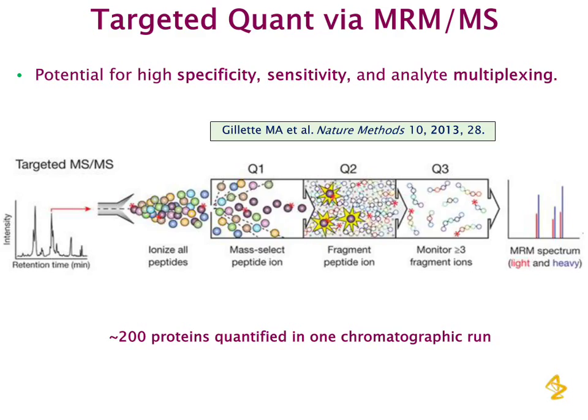Stable isotope-labeled analogs of the prototypic peptides are spiked in as internal standards that co-elute with the target peptide, and by comparing the labeled to unlabeled peak areas, a precise quantification of the endogenous peptide can be obtained.